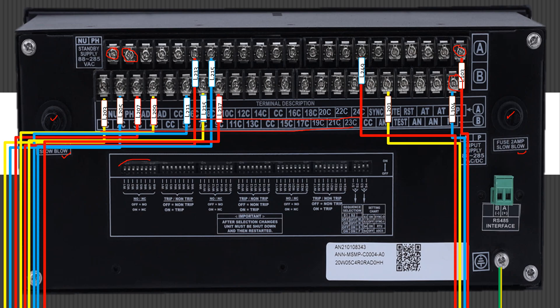Small switches in rows with C are known as DIP, dual in-line package. Tripping and non-tripping are selected by these switches — throwing the switch to ON for tripping and OFF for non-tripping. CC is the common connection. To test the fascia, that is to check the healthiness of individual windows, make a single touch with that particular contact among 1C to 24C, meant for that window, with the CC contact. By using a wire after giving power to the fascia, that particular window will blink and the buzzer or hooter will sound simultaneously.